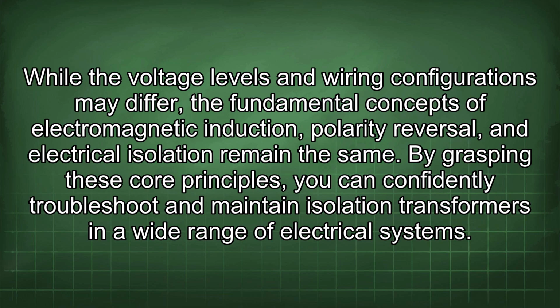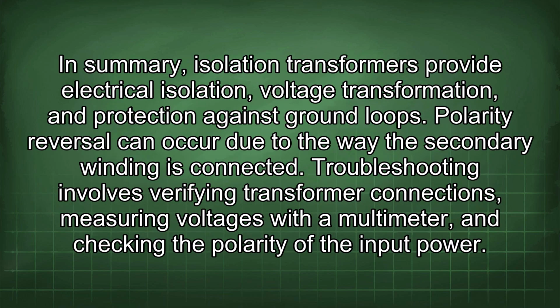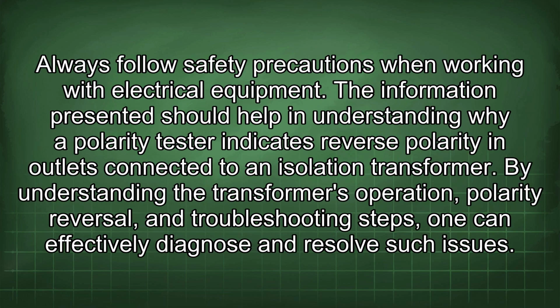In summary, isolation transformers provide electrical isolation, voltage transformation, and protection against ground loops. Polarity reversal can occur due to the way the secondary winding is connected. Troubleshooting involves verifying transformer connections, measuring voltages with a multimeter, and checking the polarity of the input power. Always follow safety precautions when working with electrical equipment.